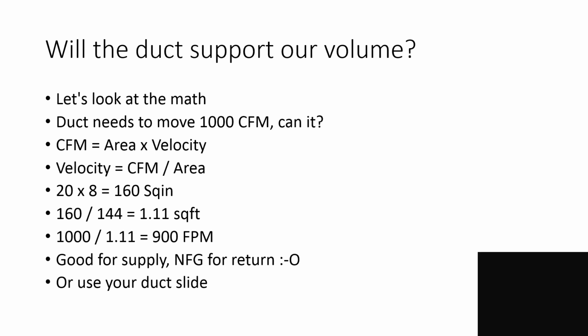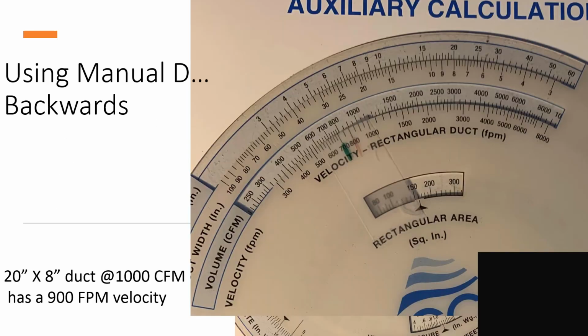Or if you don't want to do math like this and people want to use their, well, let's take our duct slides. And I want to point this out real quick. The Aqua duct slide is on the money. I have some other ones around here that were off by like 100 feet per minute. So you might want to do some math if you're not using a quality ductulator. So what I got up there right now, there's my 20 by 8 ductwork. That center section up there is our volume, or our CFM. Down the bottom is our velocity. And we see 1,000 CFM lines up with 900 feet per minute. Notice at no time did I put some BS friction rate up there that I just used as a Padoma number. Right? And there's a select few out there who might know what Padoma means.